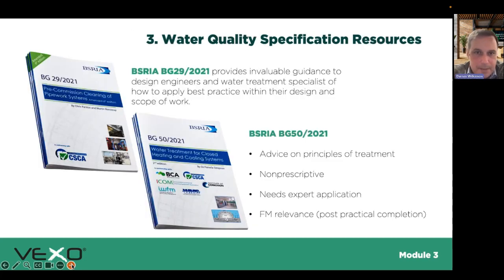So again, resources - BSRIA, if you're looking for the chemical or filtration approach, I think you should always have filtration regardless, but certainly if you're looking for a chemical approach, which is generally the most common approach in the UK, BSRIA - it's not a standard in the sense, it's a guide, unfortunately. Even in the latest publication, they try to make the point that you shouldn't be using it contractually as a standard. It is a guide, and each system and site can differ, but unfortunately people are still very much held to that number - that's what it says in the BSRIA guide.